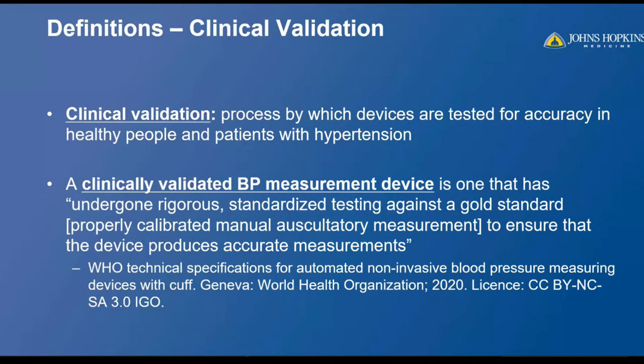Before I go on, I want to be clear on some definitions. When I say clinical validation, I'm indicating a process by which devices are tested for accuracy in healthy people and in people with hypertension. When I refer to a clinically validated blood pressure measurement device, I mean one that has undergone rigorous, standardized testing against the gold standard to ensure it produces accurate measurements. That gold standard is a properly calibrated manual auscultatory measurement.